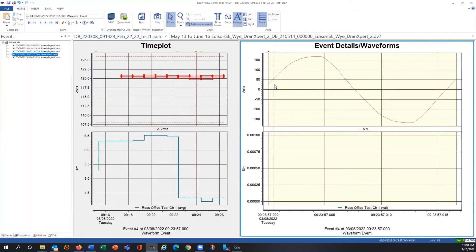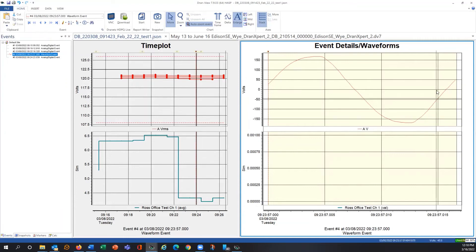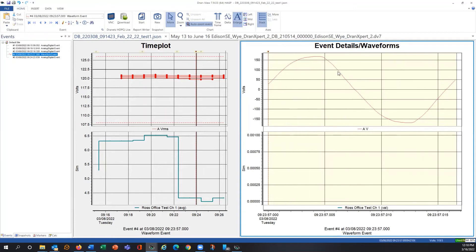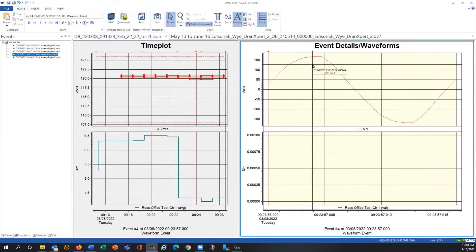Here's an example of a waveform snapshot. You can see it shows up as a waveform event, with the usual event markers in DRAN view. At this point in time I had a waveform snapshot, and you can see exactly what's going on visually. If there's any distortion, you would visually see it — and of course it would show up in THD and other harmonic parameters. You can also run this through the harmonic and time plot calculator in the full DRAN view for additional analysis.